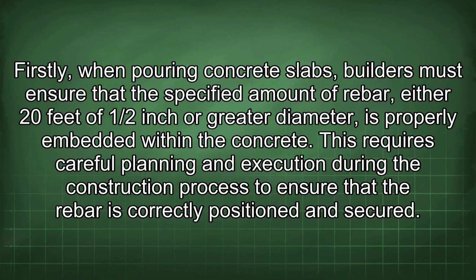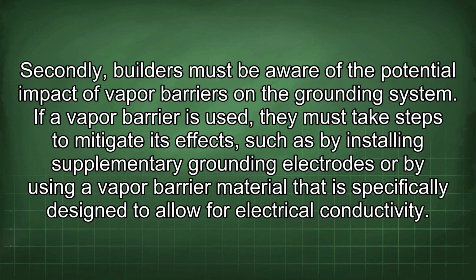This requires careful planning and execution during the construction process to ensure that the rebar is correctly positioned and secured. Secondly, builders must be aware of the potential impact of vapor barriers on the grounding system. If a vapor barrier is used, they must take steps to mitigate its effects, such as by installing supplementary grounding electrodes or by using a vapor barrier material that is specifically designed to allow for electrical conductivity.